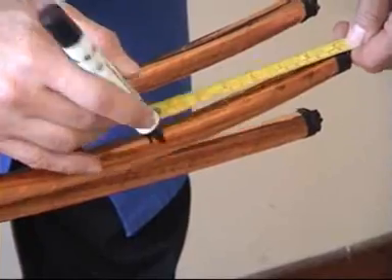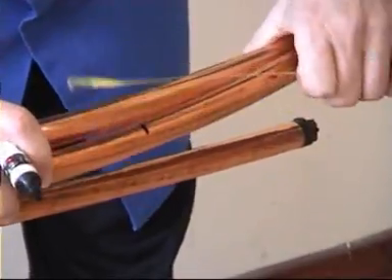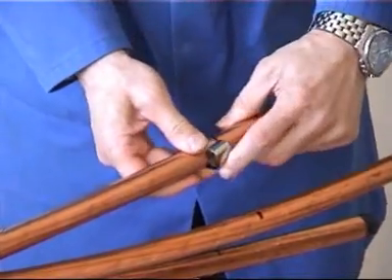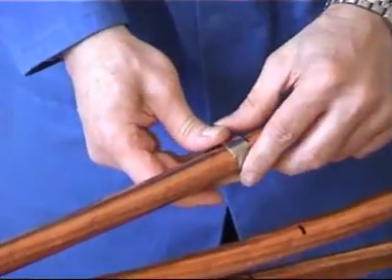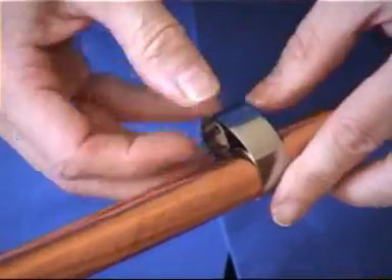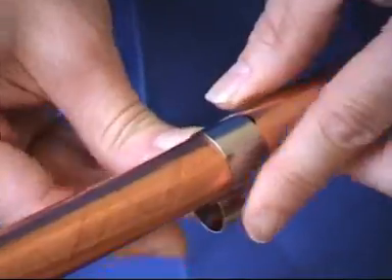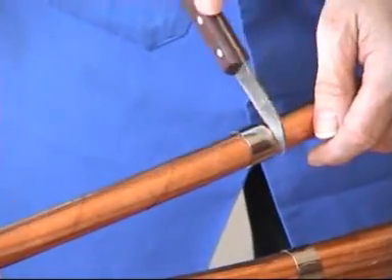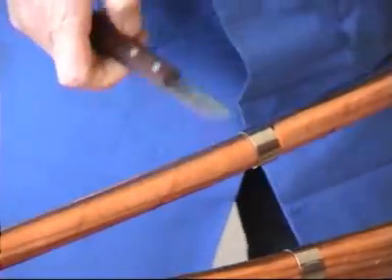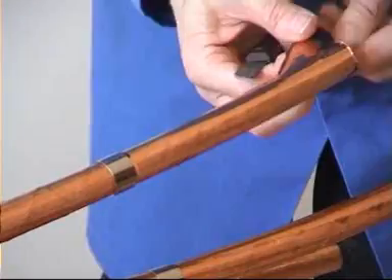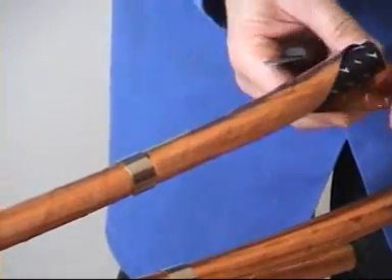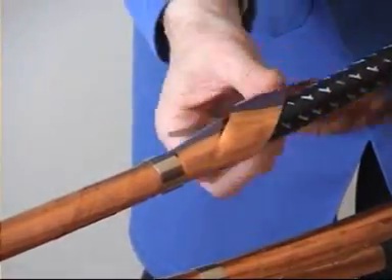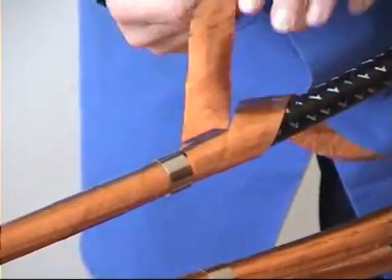Refer to the instruction and mark each core, ready for the removal of the copper tape screen. A useful trick is to apply a rolled spring at the end of this mark. And with a sharp knife, circumferentially score the copper tape. Unravel it, and tear it off carefully at this point.